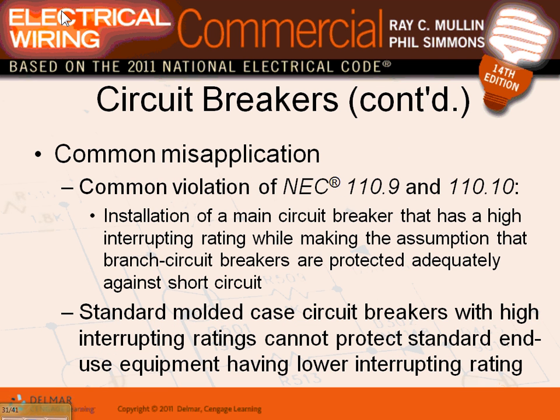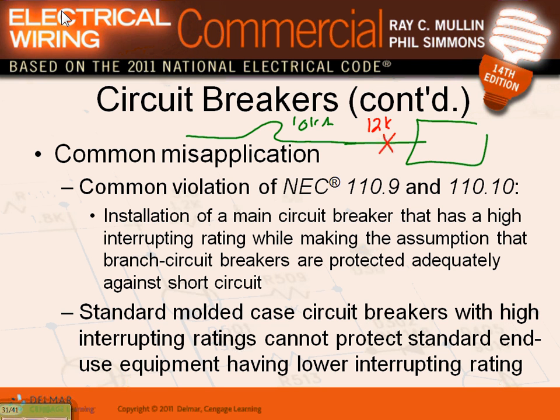Common misapplications, standard molded case circuit breakers. The very common misapplication is this: I have a 10K amp rating and my panel here is feeding an equipment, and if I do a short circuit right here, it is 12 kiloamp. That's a mismatch. What's going to happen for this circuit breaker if it tries to interrupt the 12 when it is rated 10? It's going to explode.